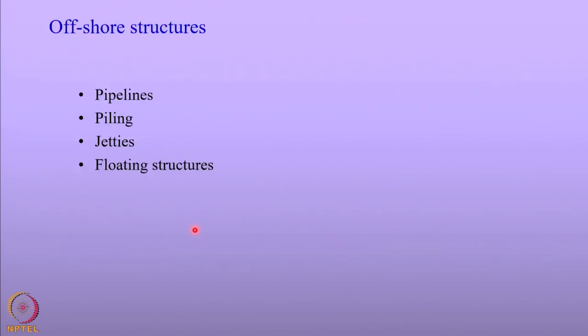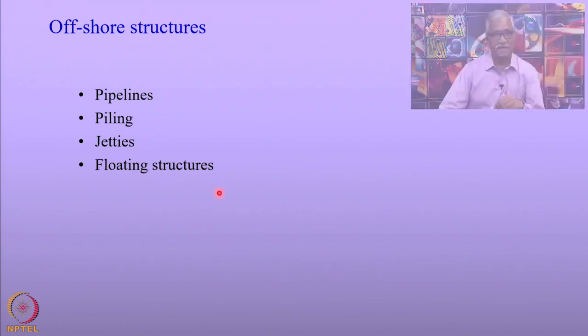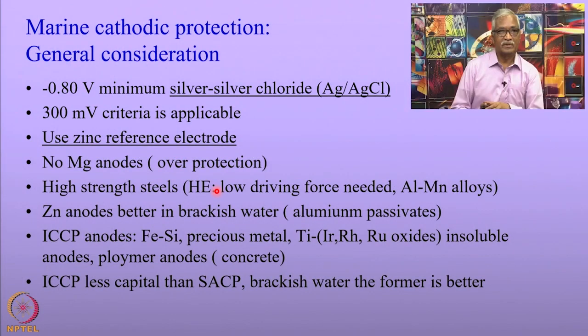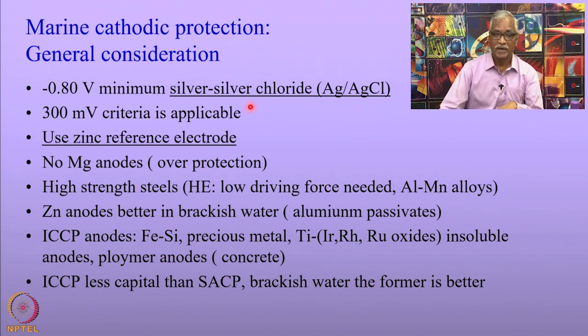Let us look at the offshore structures. The offshore structures discussed today are pipelines, pilings, jetties, and floating structures. For marine cathodic protection, the general criterion is minus 0.8 volts with respect to the silver-silver chloride electrode.